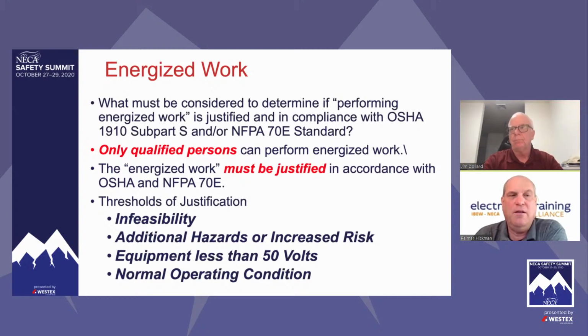So maintenance is huge, and it's a big problem. One help: NFPA 70B is now a recommended practice, meaning you should do this, you should do that. They're changing it to a standard, just like NFPA 70E, with enforceable language, the shalls. So we're going to see a lot more enforceable guidance for those that adopt 70B telling them how often and how to maintain equipment.